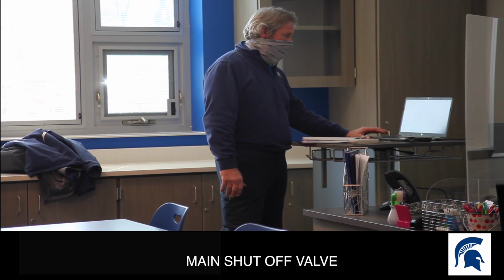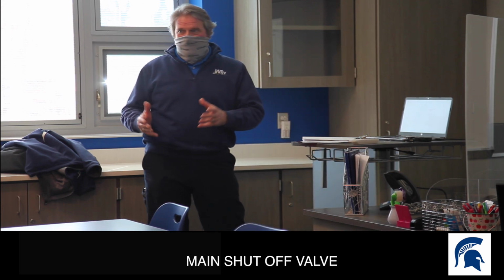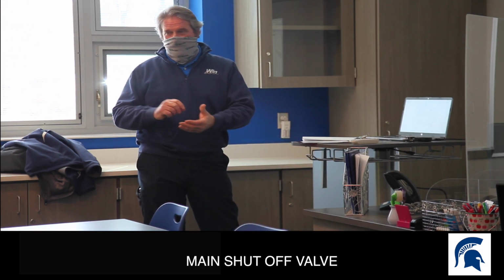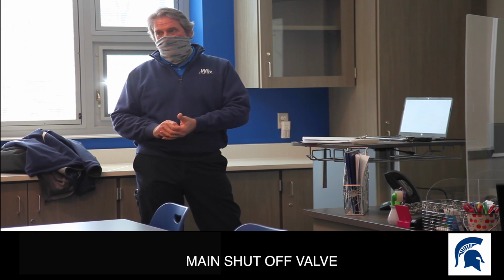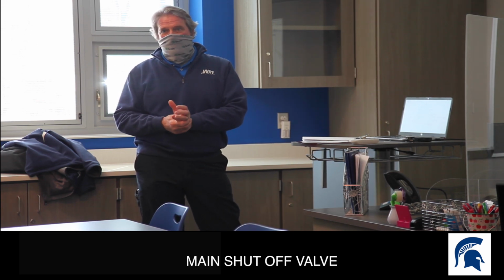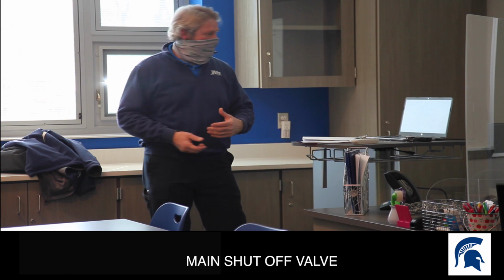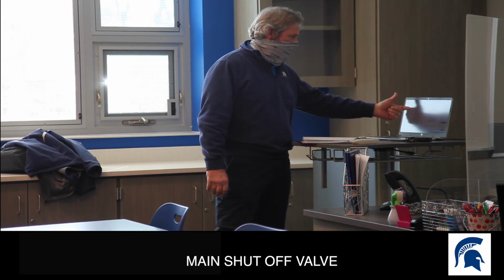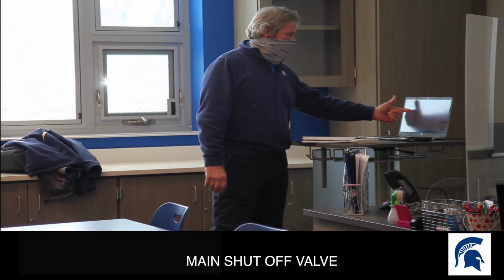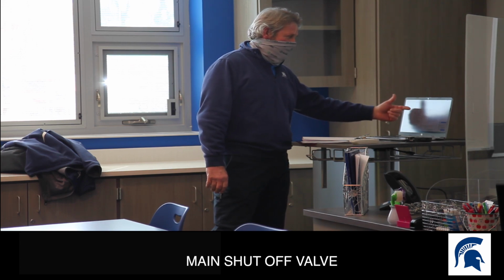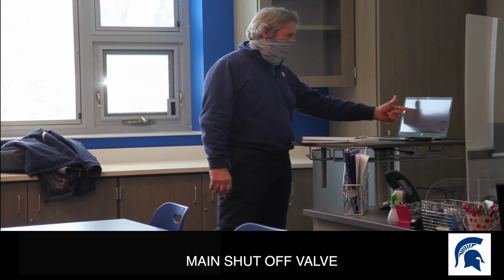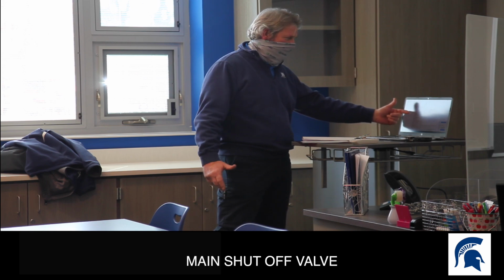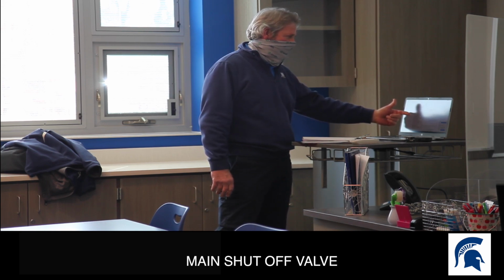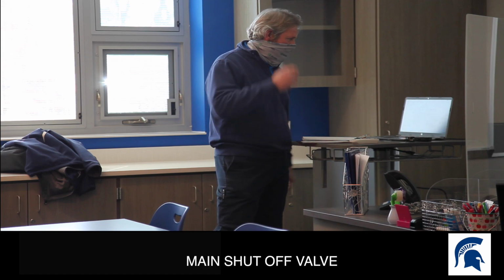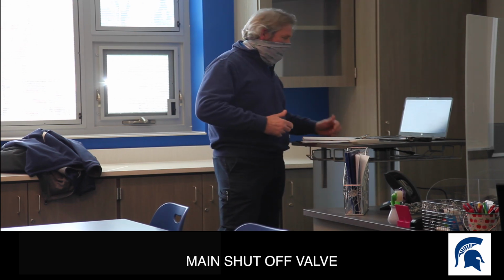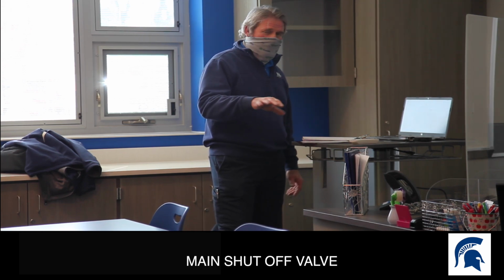But annually, you want it checked. You have to go through it, and you have to have it certified by a boiler person to keep up to date with the state. And that's what they go through here. You're still going through the same things that you're doing monthly and every 6 months, checking for leaks, verifying the flue's in good shape, nothing's blocking. All your pressures, and there should be gauges on your system as well.